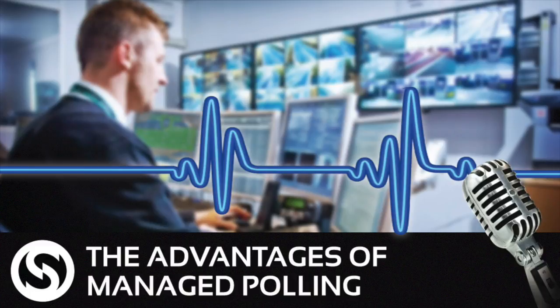Out of a block of 10,000 panels, that's a really decent amount. We've got one panel. Well, it's really zero, right? Because they're aware of that. It comes up and they go, oh, we'll just put it on hold, or, that's up to the control room. When you're talking that bigger number and that smaller amount of poll fails, that's when you can start to say, okay, our reliability levels are up there, where when you get a poll fail, it's something wrong. And in this case, that's something wrong with that panel that I was looking at there. It's got low signal. So there's not really anything wrong. It's just a case of they haven't been back out there to put a high gain on.